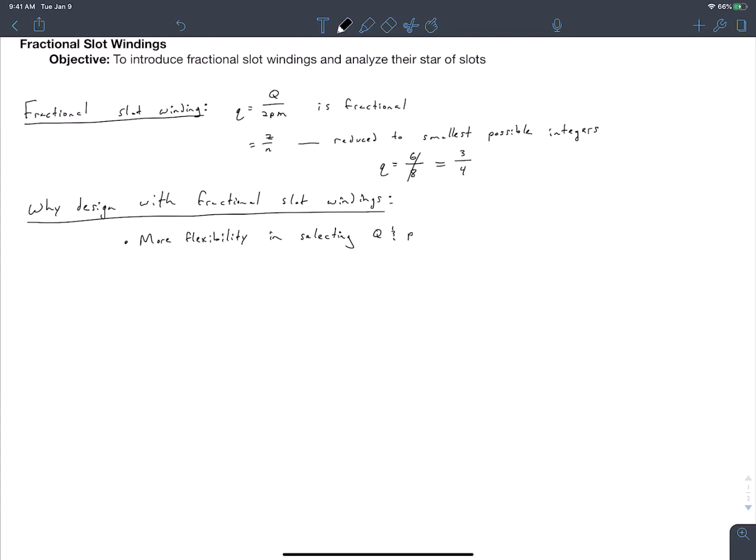For an integral slot winding, you're pretty limited by whether you can do this based on maintaining q as an integer value. For a fractional slot winding, you've got a whole lot more options because you can let q become fractional. By having more choices of Q and your number of pole pairs, you have more flexibility to design a winding that will have fewer harmonics in it.